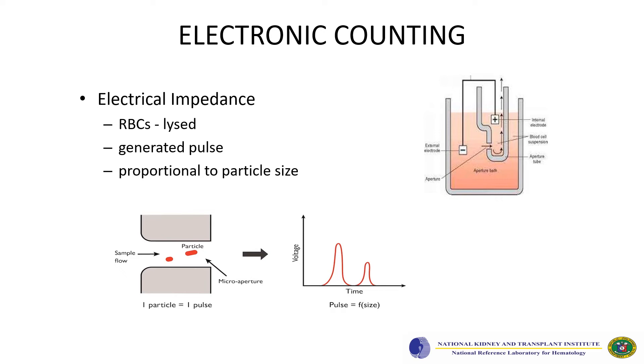Moving on to the electronic counting of WBCs, the most common technology used in a clinical hematology laboratory is electrical impedance. With the help of a sheath fluid, particles pass through an aperture one at a time, and each time a particle passes, a pulse is generated. The pulse height is directly proportional to the particle size, allowing discrimination of WBCs, RBCs, and platelets. Certain platforms require pre-lysis of RBCs before running so that the WBC count can be generated.